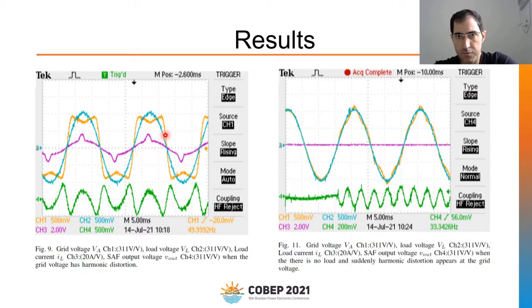The second case is two tests: no load, and also when harmonics suddenly appear in the distribution system voltage. Initially, we do not have such a distortion, which means that the series active filter is producing nothing at its output, and suddenly at this point we have distorted voltage at the distribution system, but the voltage that the loads receive is still sinusoidal thanks to the series active filter.